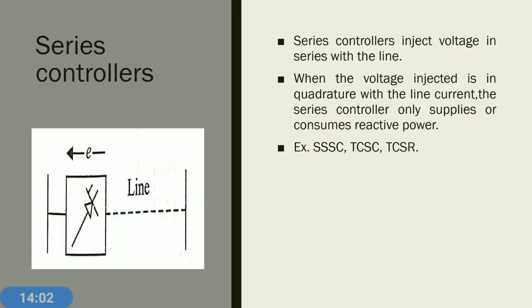The series controller is connected in series with the transmission line and injects voltage in series with the line. When the injected voltage is in quadrature with the line current, the series controller only supplies or consumes reactive power — similar to the shunt controller, which injects current in quadrature with voltage. Examples of series controllers are SSSC (Static Synchronous Series Compensator), TCSC (Thyristor Controlled Series Capacitor), and TCSR (Thyristor Controlled Series Reactor).